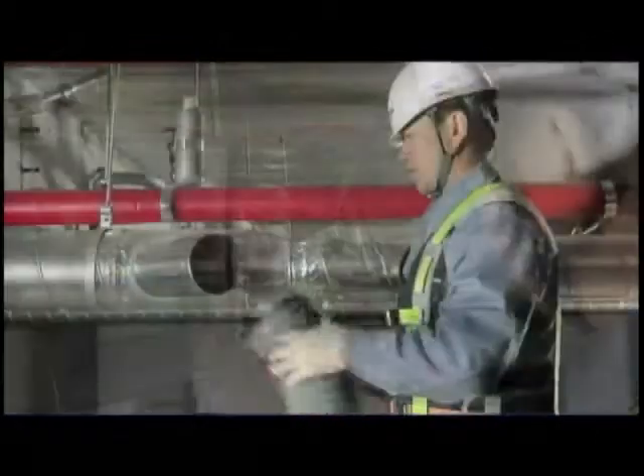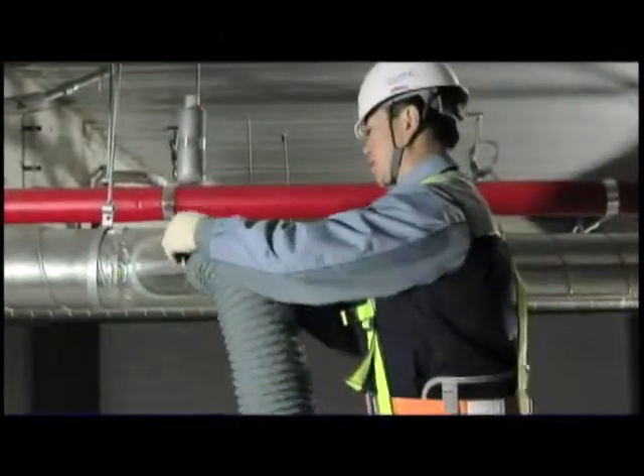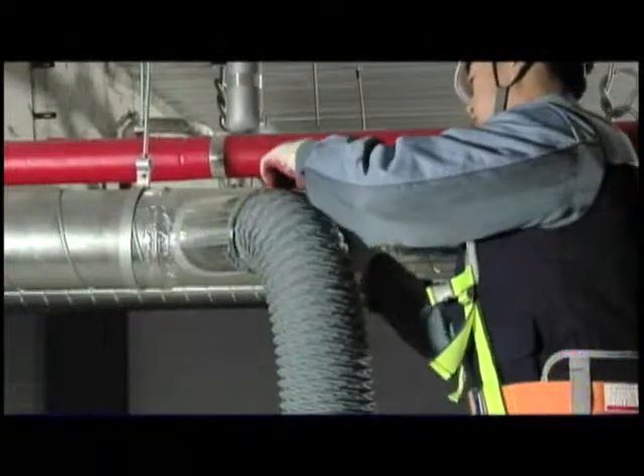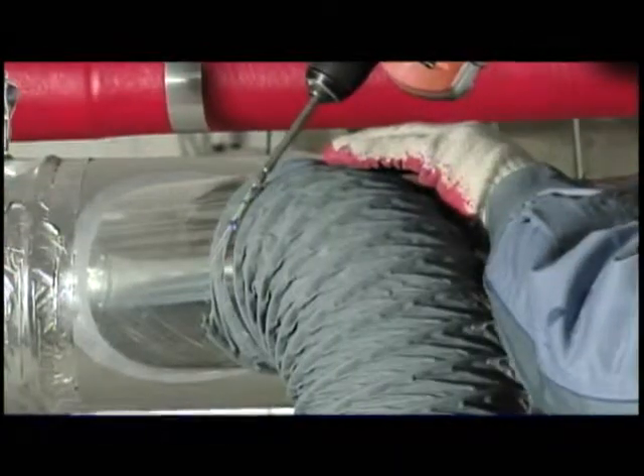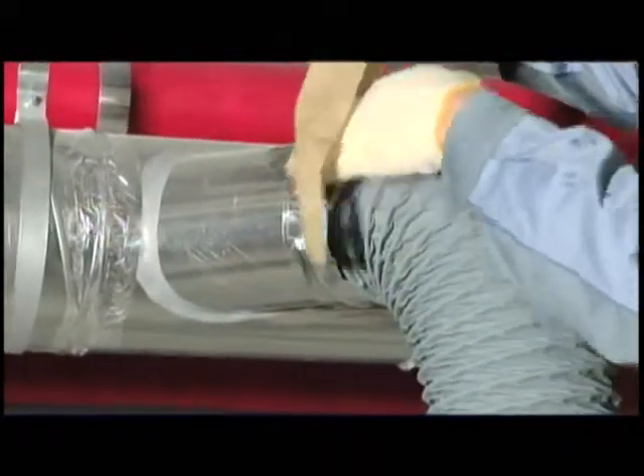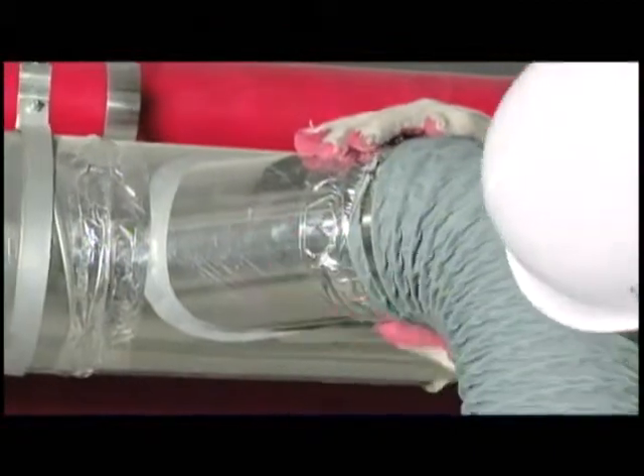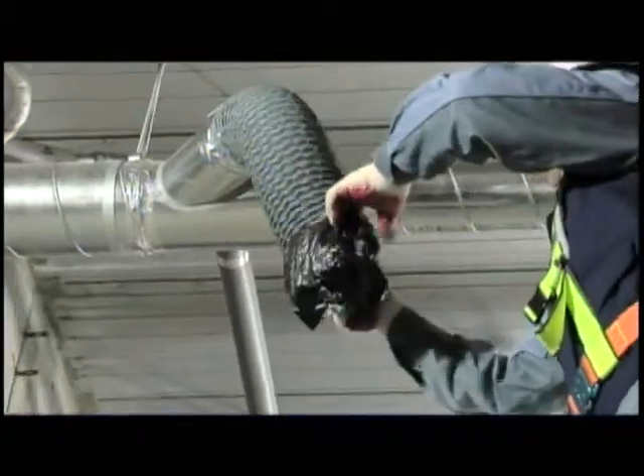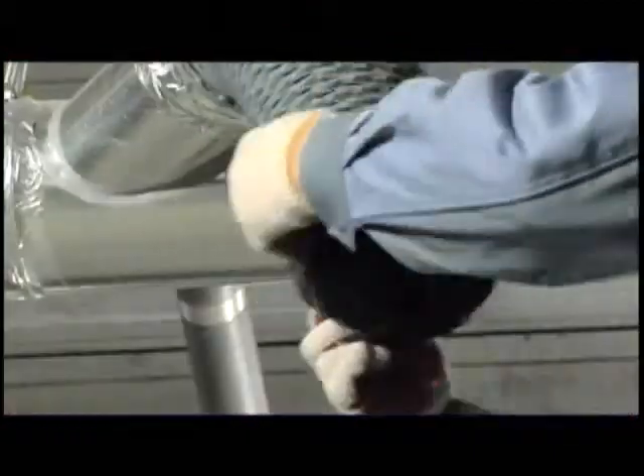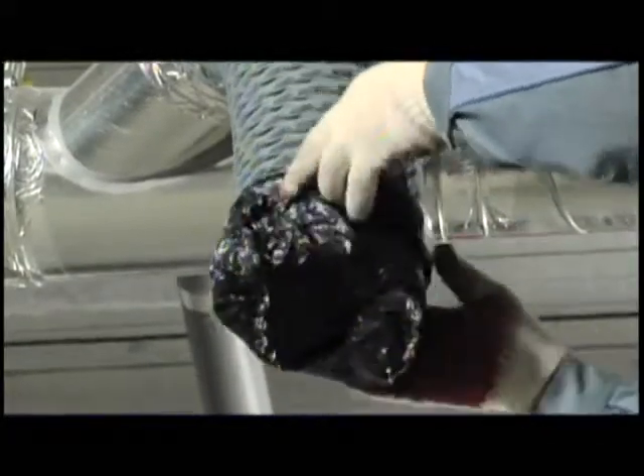When performing the ductwork, finish the joints with aluminum tape to prevent air leakage. When connecting the flexible ducts, use a clamp to connect the ducts and finish with aluminum tape and reinforce the areas to prevent entry of dust.